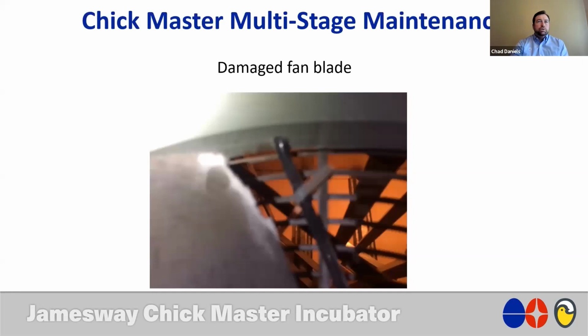Another situation we see a lot of times with a fan is here you can see where the tip of this blade has been damaged. Anytime that you have damage to a blade, it will affect its ability to create static and move air properly.